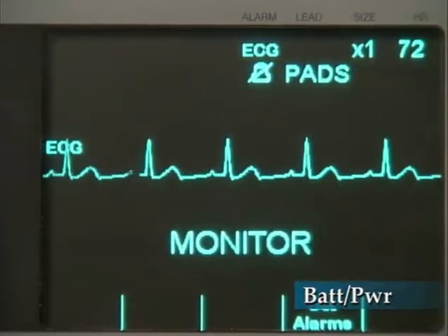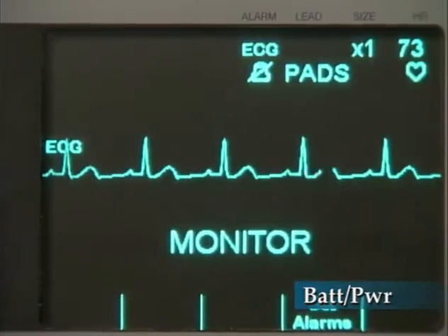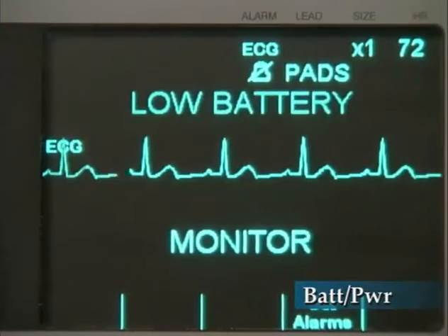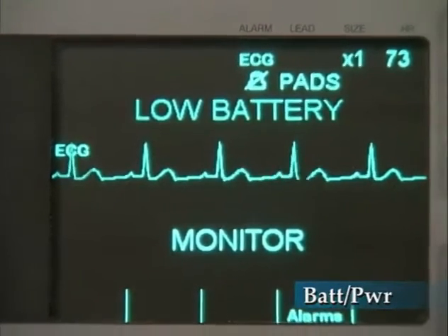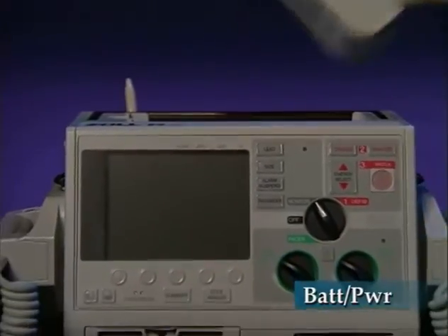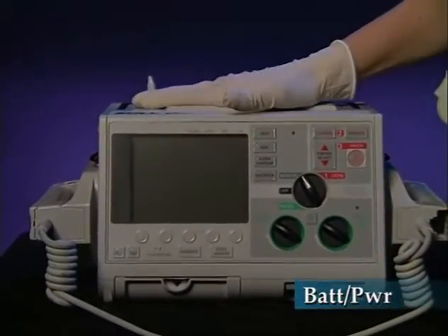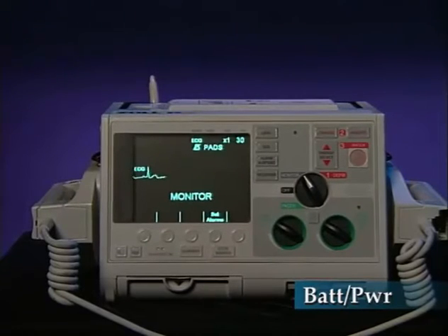When operating on battery power, a low battery message will be displayed on the monitor and a 2-beep tone will sound once a minute when the battery is low. Replace the battery pack immediately or plug the unit into an AC or DC power source to ensure continuous operation. All settings will be maintained for 10 seconds while the batteries are exchanged.